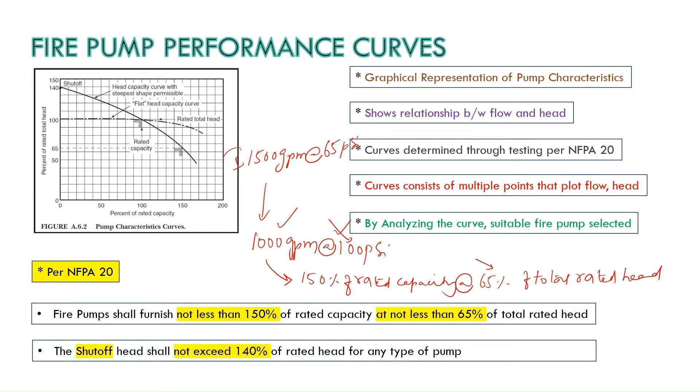So this is the first criteria we need to satisfy to comply with NFPA 20 requirement and the second criteria is the shutoff head. Shutoff head shall not be more than 140% of the rated head for any type of pump. So we have our total rated as 100 PSI so our shut off head shall be less than 100 into 140% which will be around 140 PSI. This might vary based on the pump manufacturer curve however the pump shall not produce the shut off head more than 140% at zero flow condition.